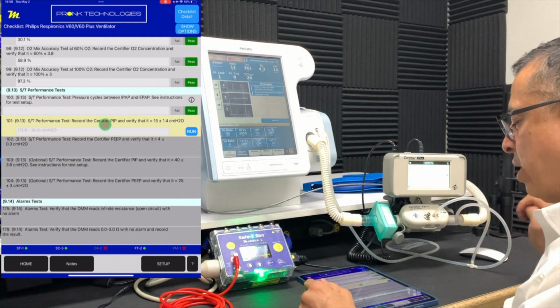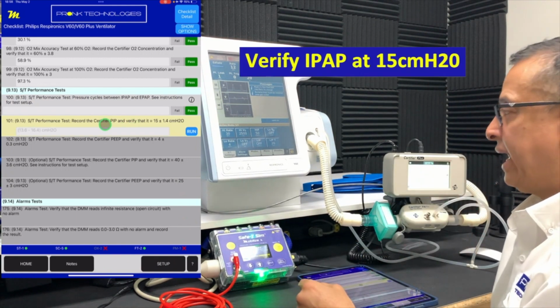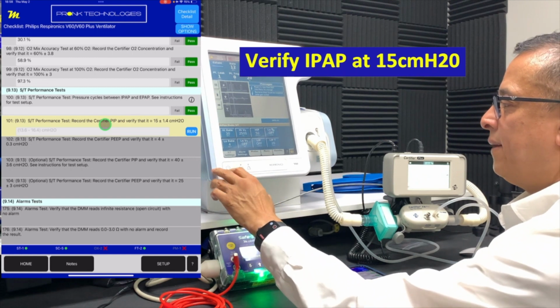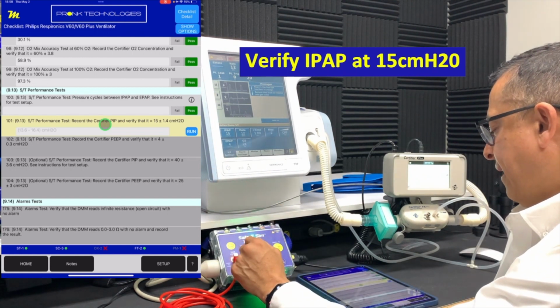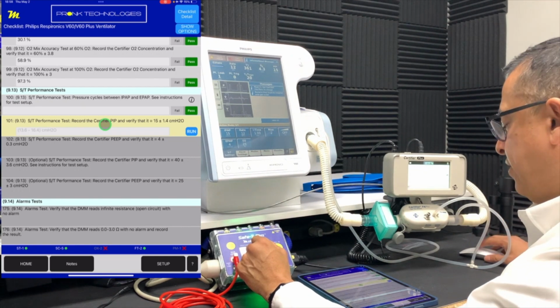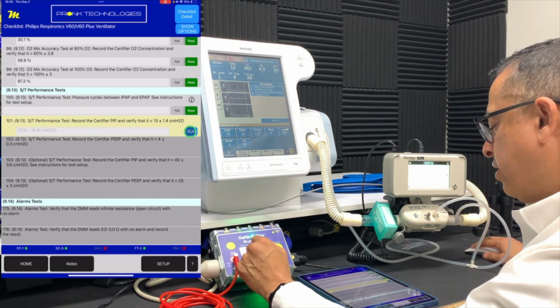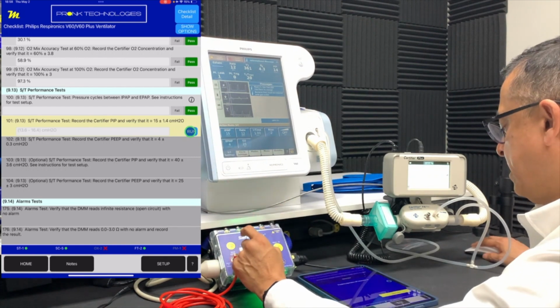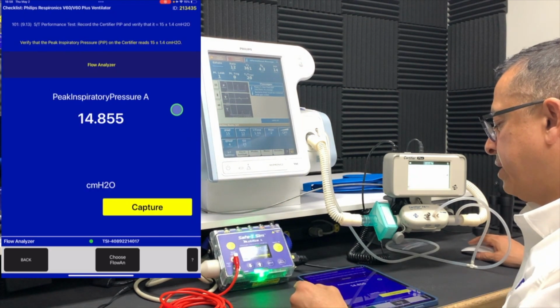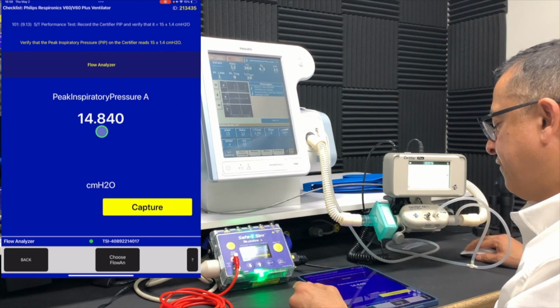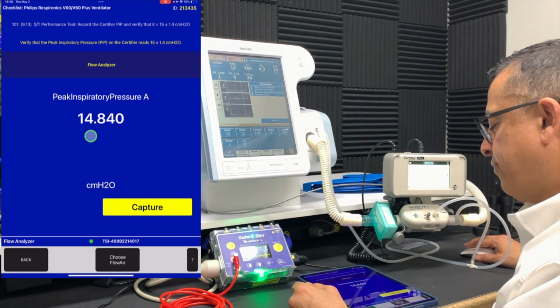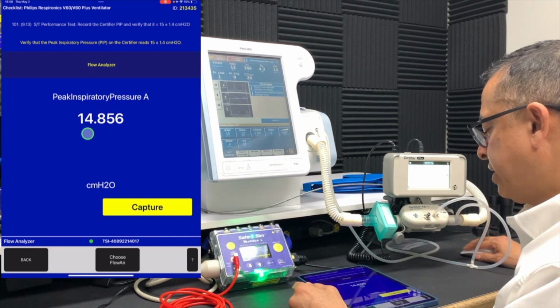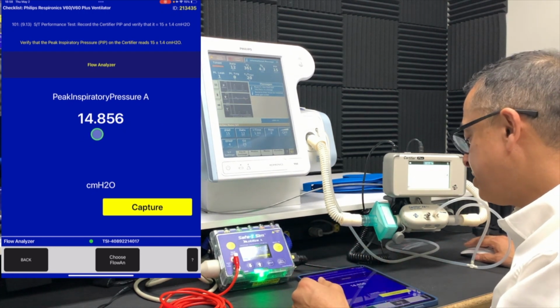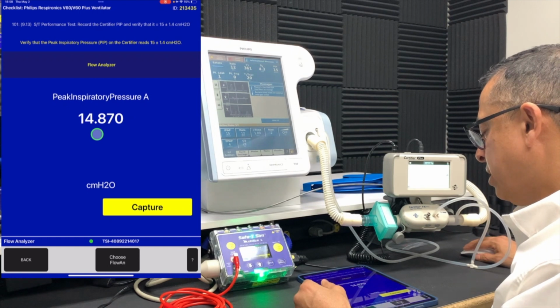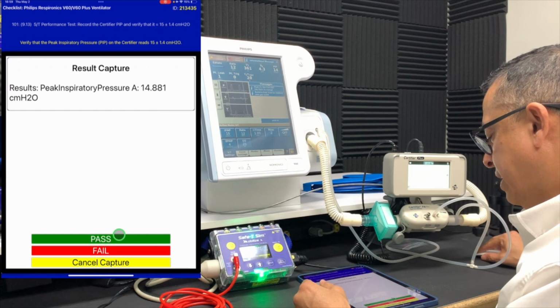So the first test we want to do is to perform this test at an IPAP of 15, and we want to make sure that the value is within plus or minus our tolerance here. So we're going to go ahead and run that test. We've got it set for 15, and we're going to make sure we measure our peak inspiratory positive airway pressure at 15 plus or minus 1.4. We're pretty close here. We'll monitor it for a moment, make sure it stays within tolerance. We don't want to take a momentary value. So in observing it, it looks pretty stable at that value. We're going to go ahead and capture that value, that test pass.